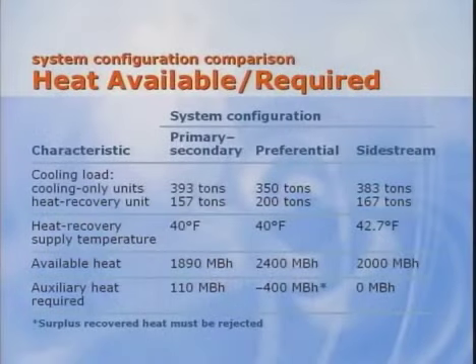The cooling-only chillers must be selected for the design delta T, even though they will experience a reduced delta T whenever the heat recovery chiller is running. One way to correct the imbalance in flow is to increase the flow rate through the operating cooling-only chillers. A control sequence must be set to increase the chiller flow as the return water temperature to the chillers increases. Of course, the chiller pumps must be selected for the increased flow, and the flow can't exceed the maximum allowed for the chiller. This slide shows a summary of the load conditions for our example.